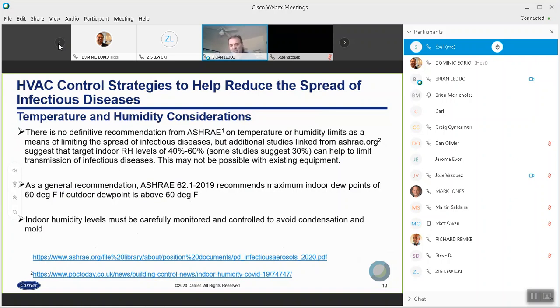linked from their homepage that point to a study from a site called PBC Today, and also they have a document called the PD sheet relative to infectious aerosols. Both of those are linked, and they do suggest that humidity levels between 40 and 60% might be beneficial. Now, the negative side of that is you might not be able to achieve that with the equipment you have. A lot of facilities don't have any means for humidification. In colder climates, you'll have issues with condensation on windows and things. So again, like a lot of aspects of this guidance, applying it in the real world is likely going to be challenging in some cases.